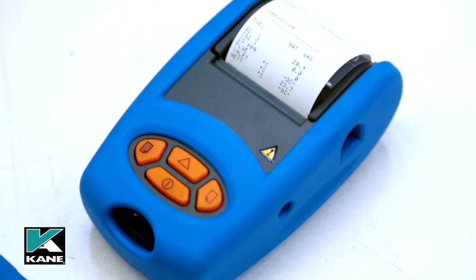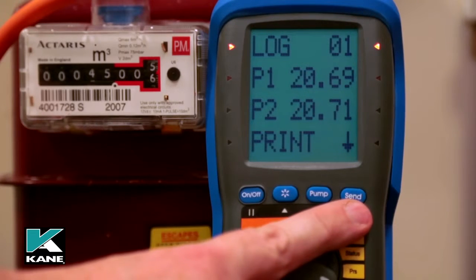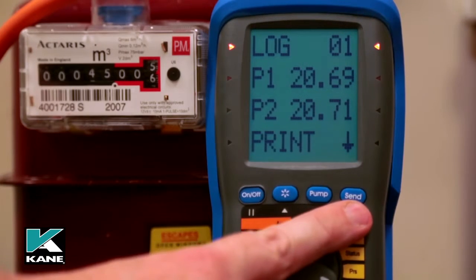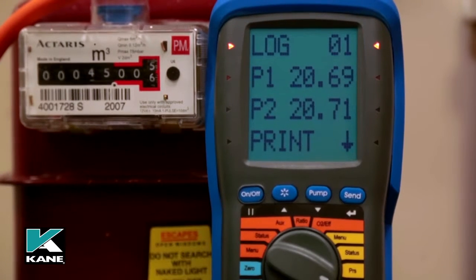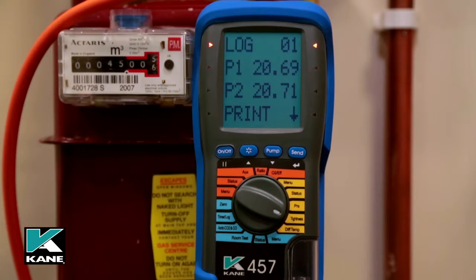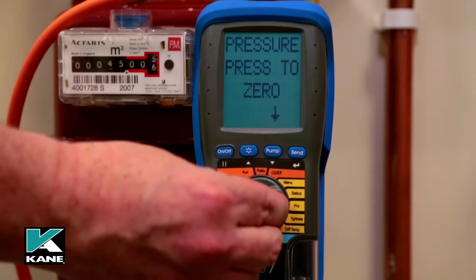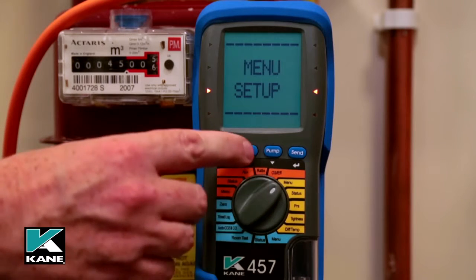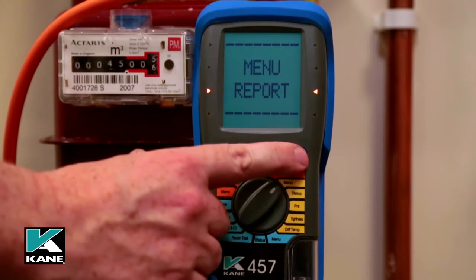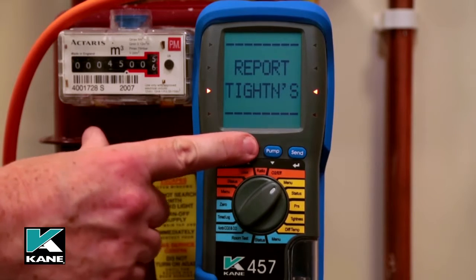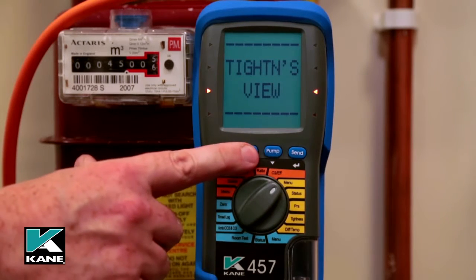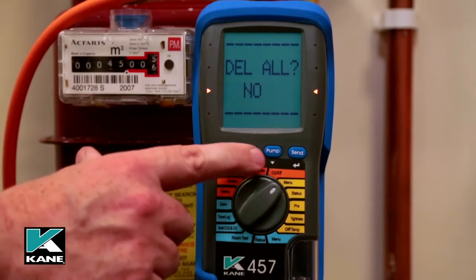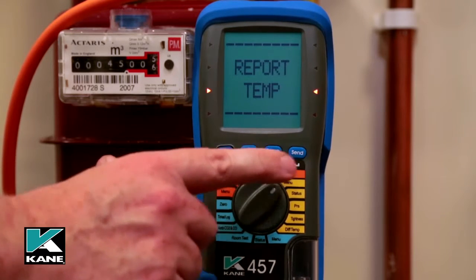The analyzer's memory can store up to 20 tightness tests. Tightness tests are logged automatically, therefore the tightness section of the memory will be full after the 20th tightness test is complete. Once full and before any further tightness test can be performed, the tightness section of the memory must be cleared. To do this, select Menu, Report, Tightness, delete all, Yes, then press Send.